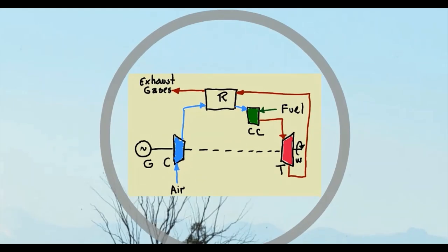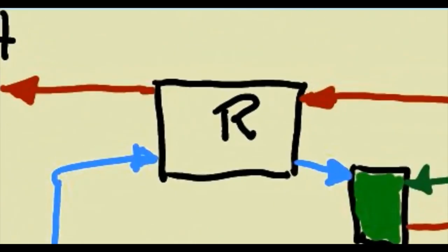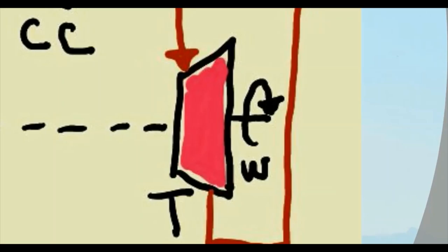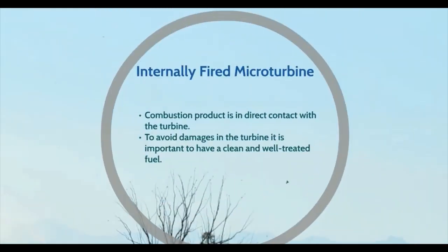Internally fired microturbines typically have a recuperated cycle, and their components are a compressor, a recuperator, a combustion chamber, a turbine, and an electric generator. The cycle starts in the compressor, which takes air at atmospheric pressure. The compressed air is then directed to the recuperator, where the temperature is increased. The compressed and preheated air is then sent to the combustion chamber along with the fuel. The products of combustion go to the turbine, where the gas is expanded, producing the rotation of the turbogenerator shaft. The expanded flue gas goes to the recuperator to transfer heat to the cold compressed air. Finally, the high temperature exhaust gas can still be used in other thermal applications.